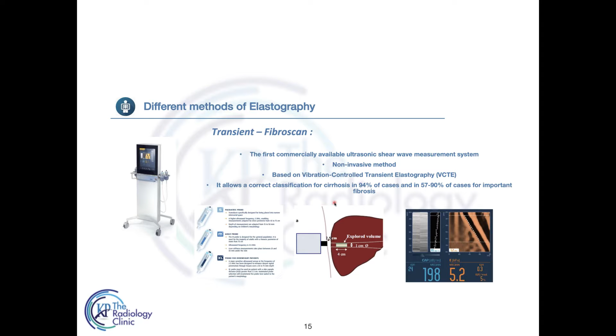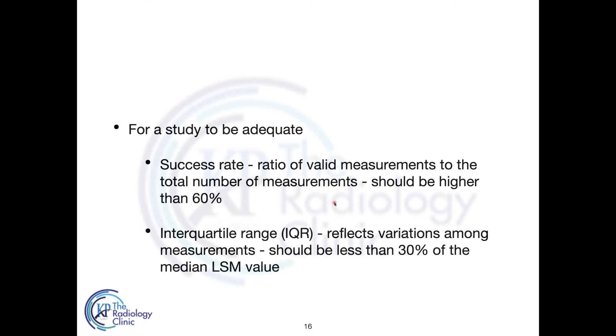For a study to be adequate, the success rate, which is the ratio of valid measurements to the total number of measurements, should be higher than 60%. The interquartile range reflects variation among the measurements, and it should be less than 30% of the median liver stiffness measurement values. Some of the limitations of transient elastography are: it is a blind technique.